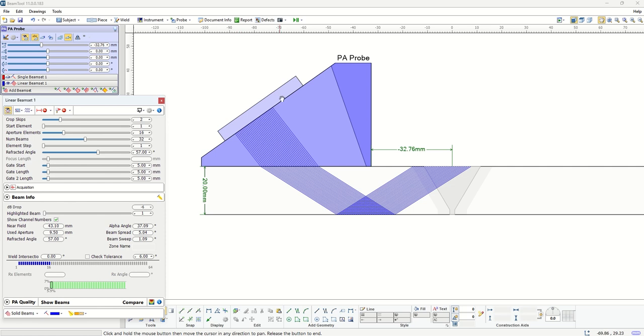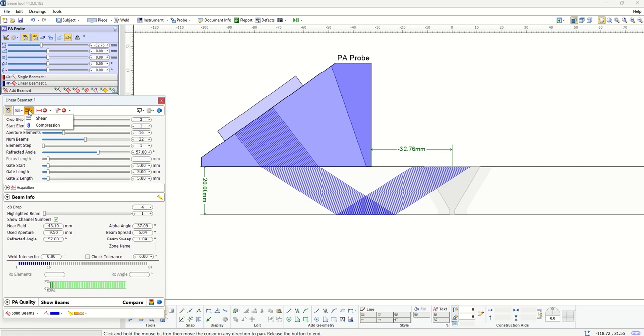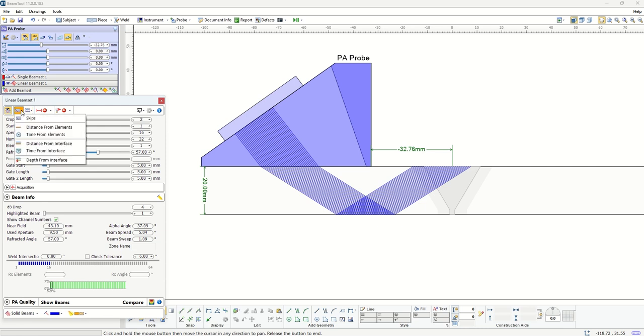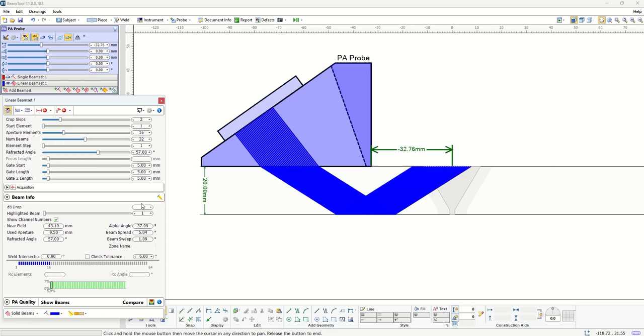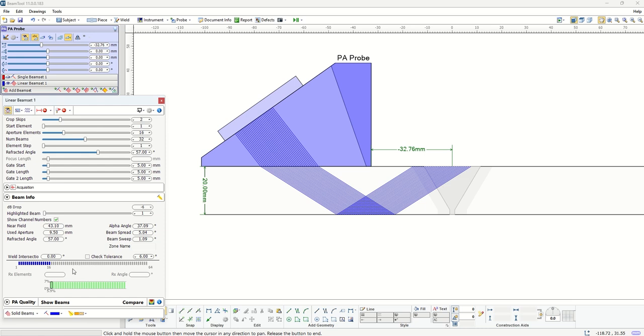As we increase this, it basically repeats generating that beam with different apertures in the probe, but all the angles that are generated would be the same angle. All these beam sets will share the same features as we showed before in terms of choosing the wave mode, defining the propagation path, gates and focusing.